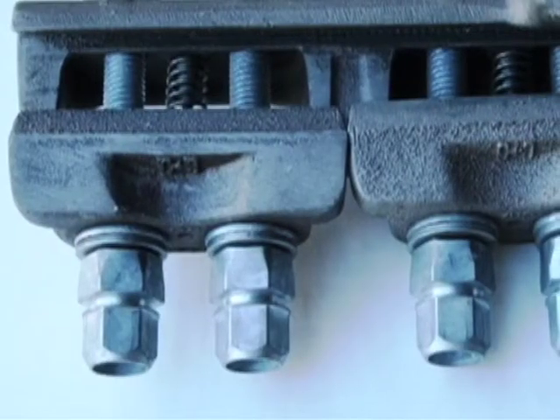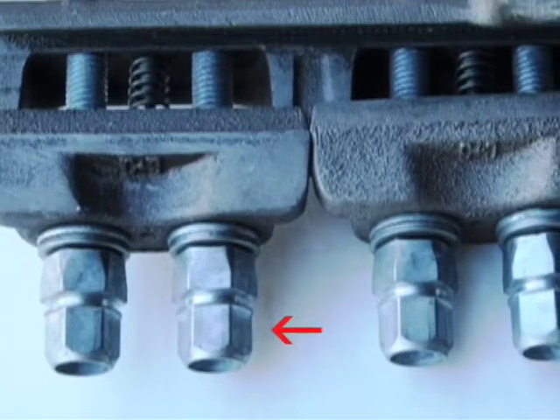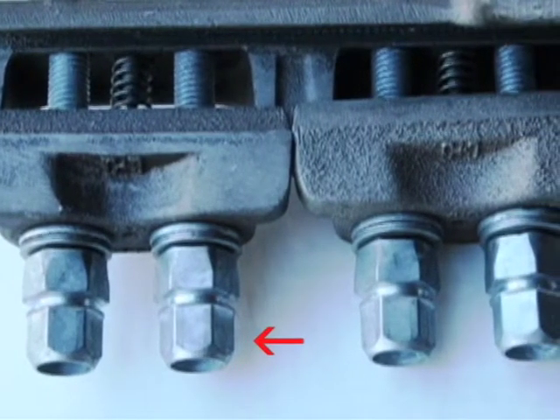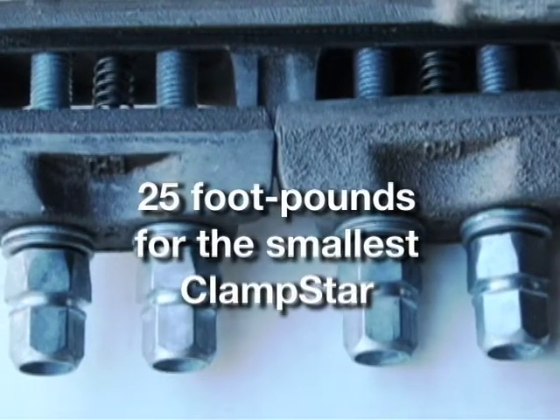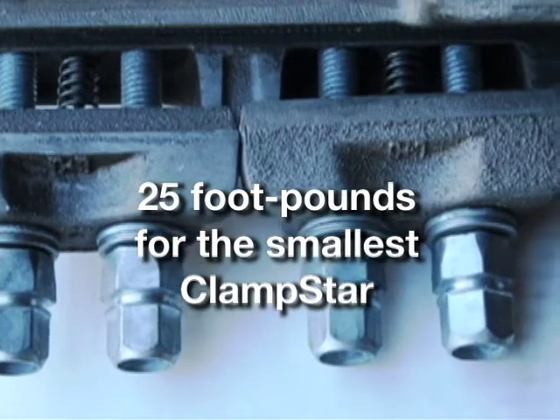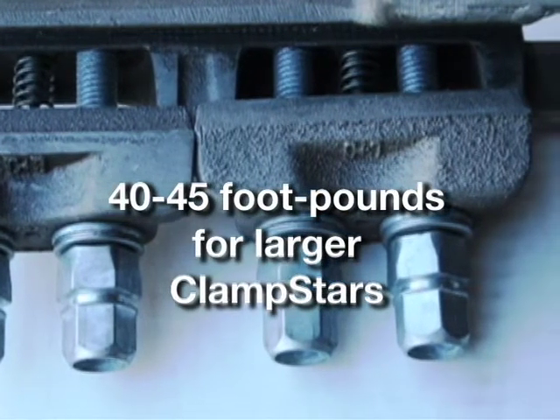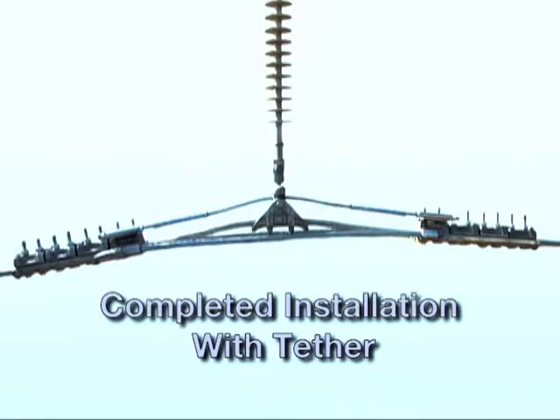All ClampStars are supplied by the factory with pre-installed torque limiting nuts containing a top section that is designed to snap off when the correct torque level is reached: 25 foot-pounds for the smallest ClampStar CSR 0325 with 3/8-inch hardware, and 40 to 45 foot-pounds for larger ClampStars with half-inch hardware. Complete an installation with tether.